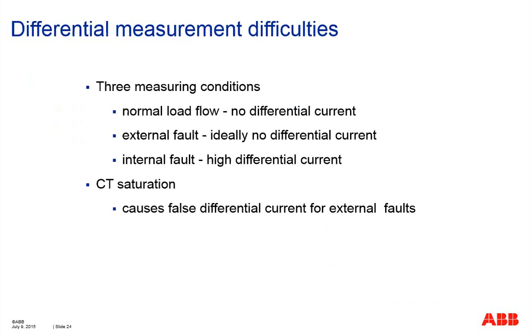So there are in general three conditions. This is basically applied in general to any differential type of measurement philosophy. Basically, under normal load flow, there should be no differential current. The relay should be stable. Under external fault, there will be high current flow through the zone. However, because it's in and out, your differential protection has to be stable as well.